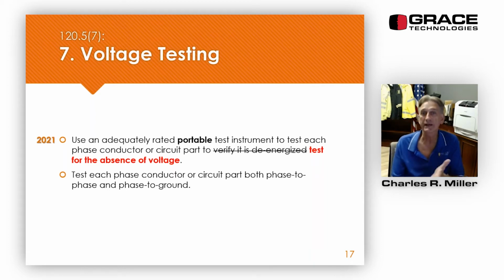Well, how do we do this? It goes on to tell us we test each phase conductor or circuit part. We do it phase to phase and phase to ground. So if it's 3-phase, we're testing A to B, A to C, B to C, and then A to ground, B to ground, and C to ground.